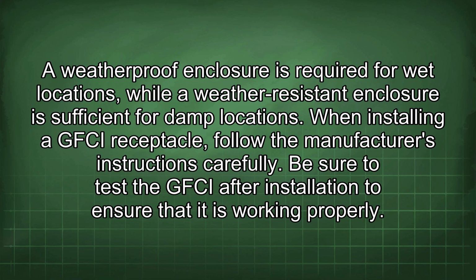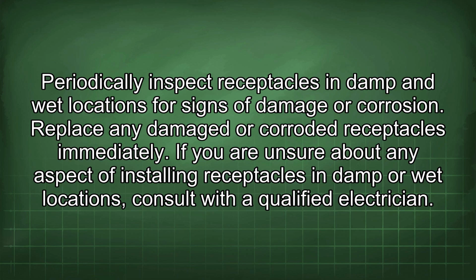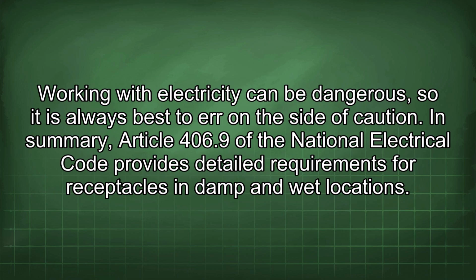When installing a GFCI receptacle, follow the manufacturer's instructions carefully. Be sure to test the GFCI after installation to ensure that it is working properly. Periodically inspect receptacles in damp and wet locations for signs of damage or corrosion. Replace any damaged or corroded receptacles immediately. If you are unsure about any aspect of installing receptacles in damp or wet locations, consult with a qualified electrician. Working with electricity can be dangerous, so it is always best to err on the side of caution.